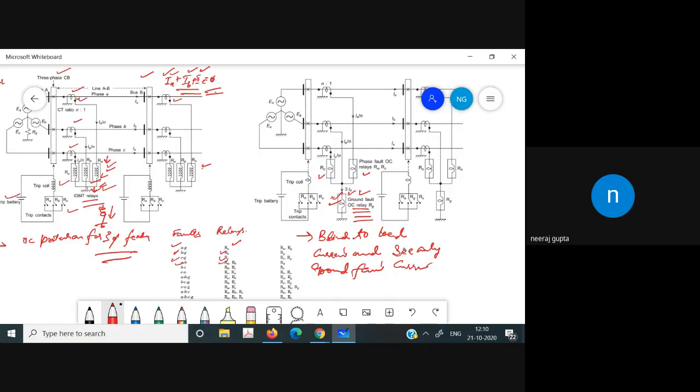Let us suppose this is phase A, then we have phase C, and then the ground path, where we can use the relay. Then instead of three relays, we use two relays and one relay in the ground path, and it will serve the purpose without affecting the performance of the system. So relay B in this case can be removed.